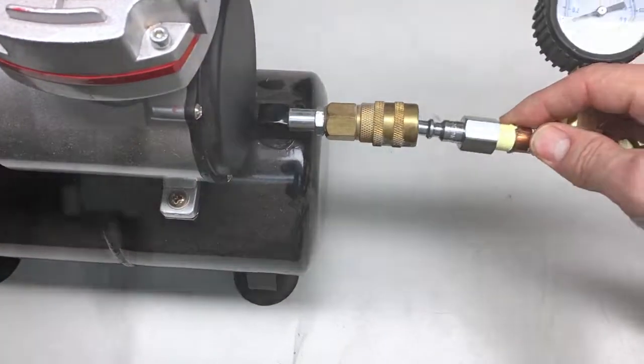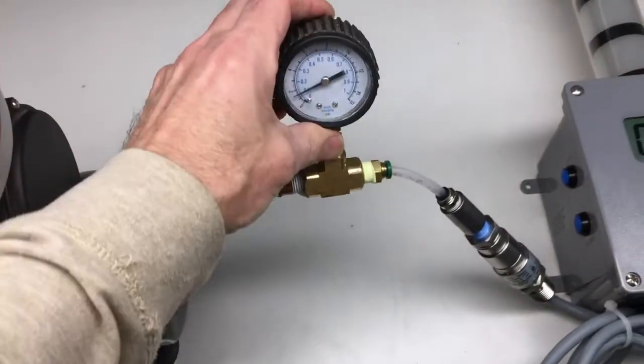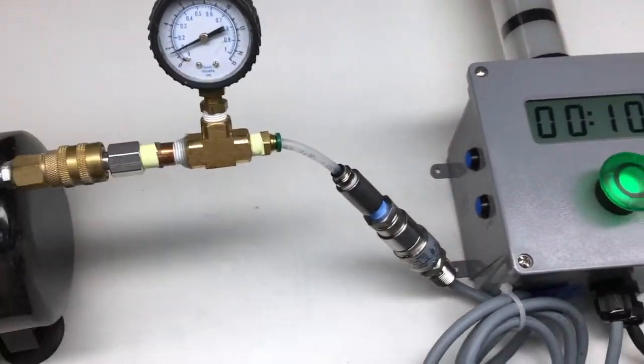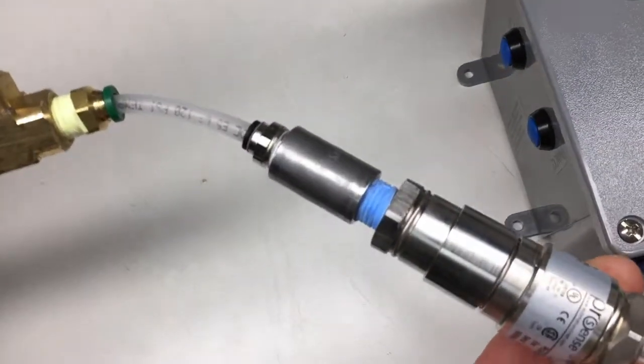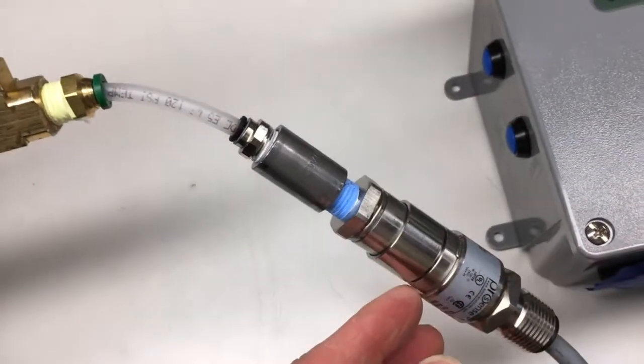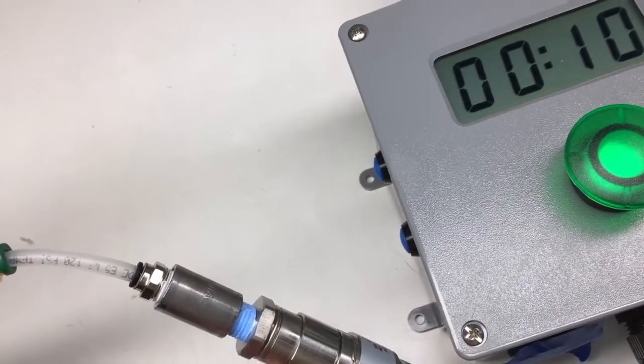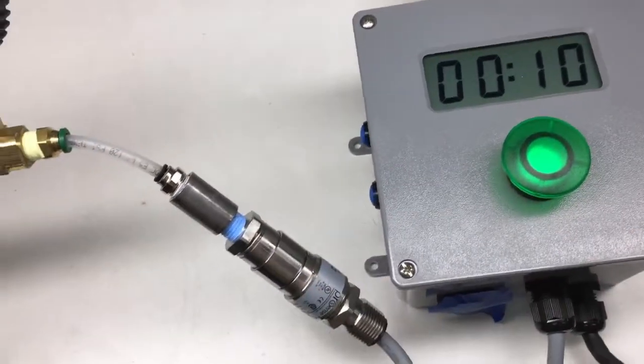So what I'm going to do is plug this in and what we'll see is when the pressure gets to 10 psi, in the case of this pressure switch, it's a ProSense. When it gets to 10 psi it'll close a switch which will activate our timer.